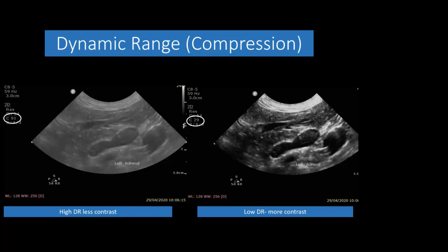And then there are other settings in the machine that you can twiddle with and change. Dynamic range is one of them, and here's a good example on the left. This left adrenal is running at a higher dynamic range, so what you get is a less contrasty image, but more fine grayscale. Whereas with a lower dynamic range, you've got a very, very contrasty image, very black, and the white is very white. So I would argue that a lower dynamic range is probably useful for looking at the heart, whereas a higher dynamic range or compression is useful for looking at fine differences in grayscale. For an abdominal scan, I think that's something that would be useful to change. So it's about being able to understand what these different buttons do when you change them.